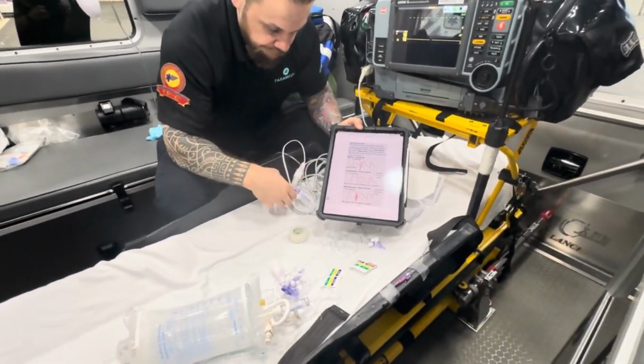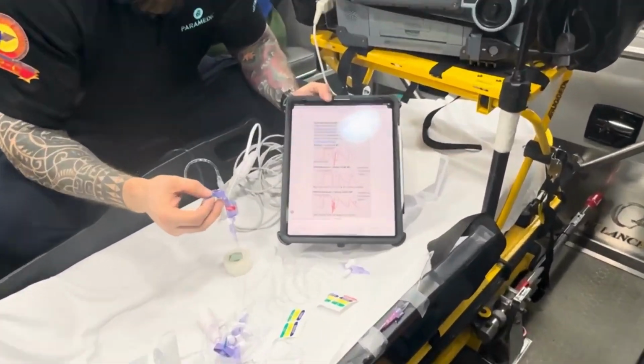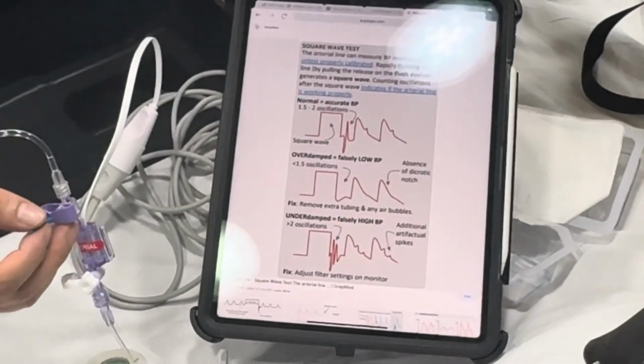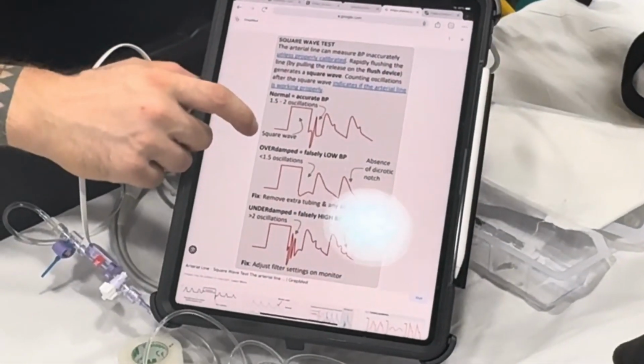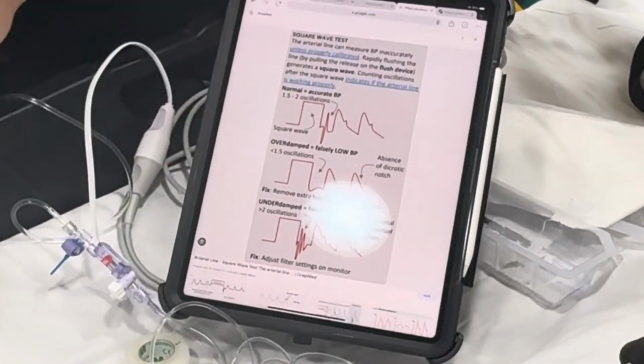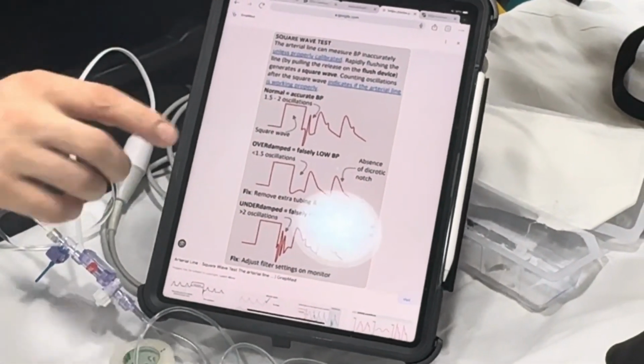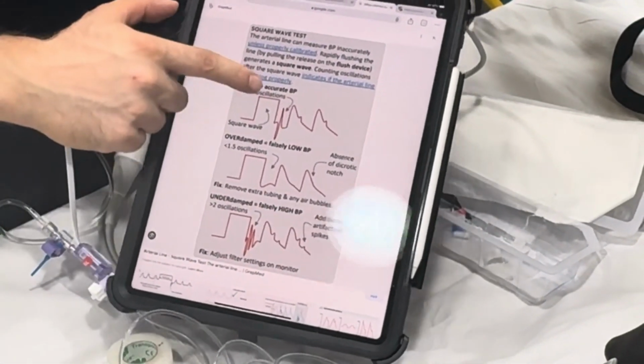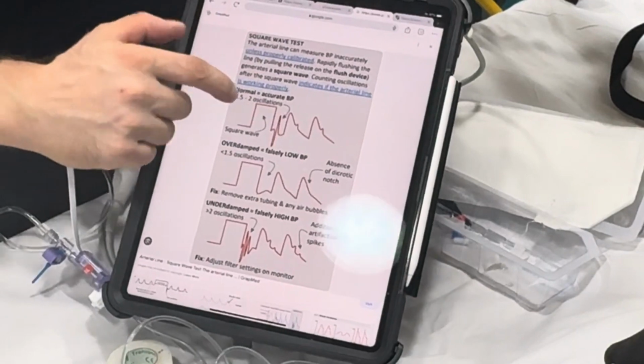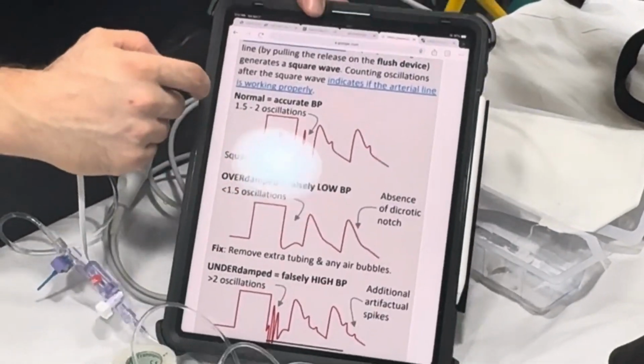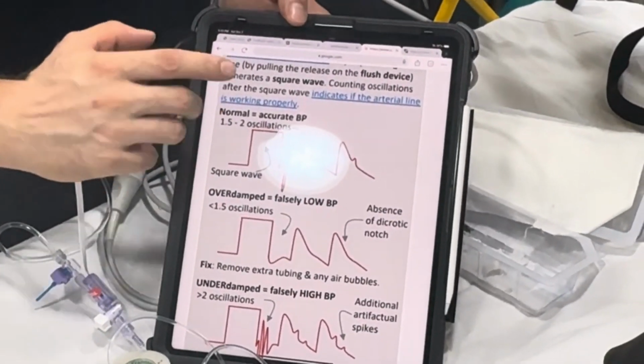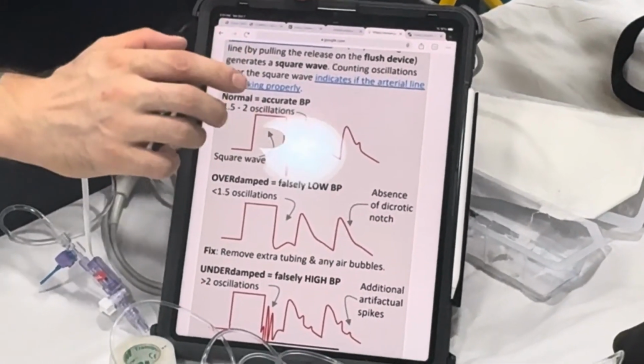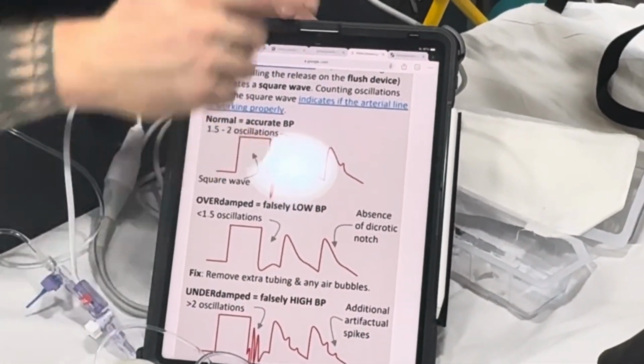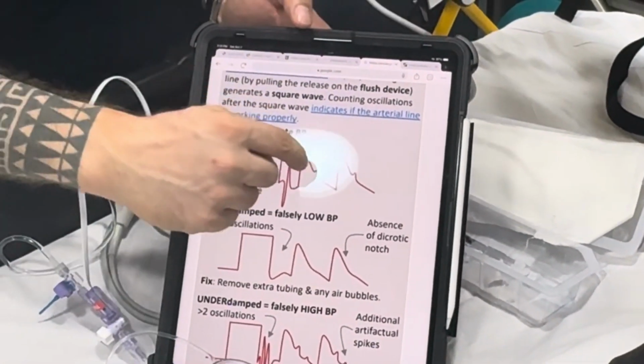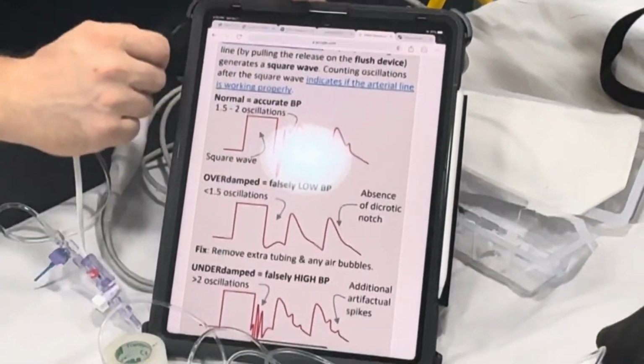So how would you perform a fast flush test? I'm going to quickly pull on this pigtail, and when I do, you'll see what appears as a square wave. Why? Because I'm basically infusing saline into the arterial line. And what you want to see is 1.5 to 2 oscillations. 1.5 to 2 oscillations means the system is properly damped, so you're getting the most accurate blood pressures, and you're going to see a good waveform like this on your monitor with a dicrotic notch, which indicates closure of the aortic valve.